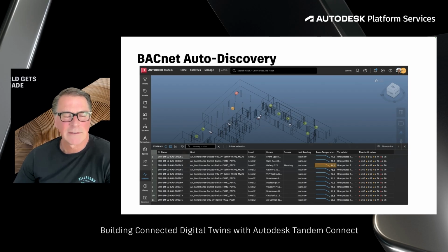So the first thing is the BACnet devices. If you don't know what BACnet is, it's a protocol for reading the information that goes through the building management system. So things like the temperature sensors in the building, CO2, humidity, there's all these sensors that are in all of the rooms and spaces. And they report back to the building management system through some protocol called BACnet, which runs on the network, but not on the internet. So it's on the private network of the building, usually on the subnet that's very secured and walled off.